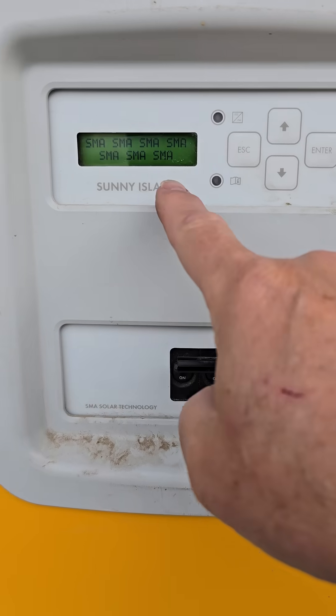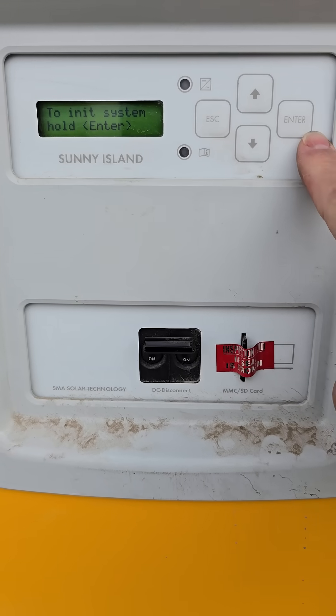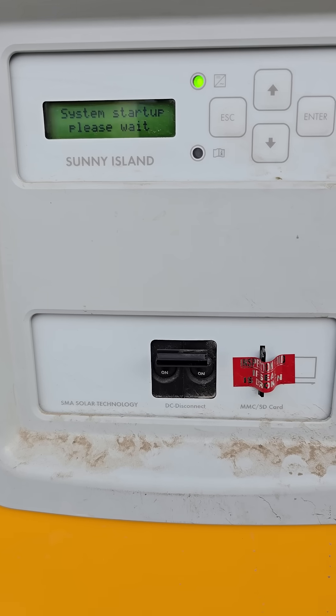Let's go ahead and turn it on. When it turns on, it's going to do the init — this is the important thing. You got to wait. You do not want to press and hold enter. Right here it says 'init system.' You do not want to press enter right here, or else you'll go into the init mode, and that has its own complications. I have videos on that.